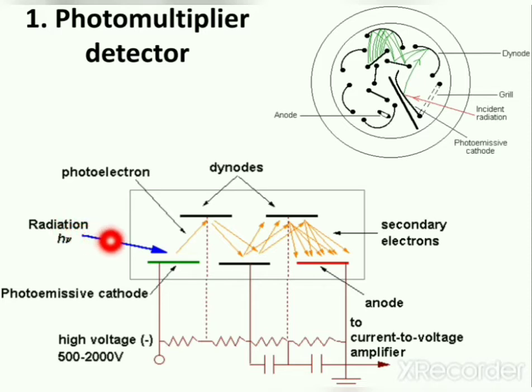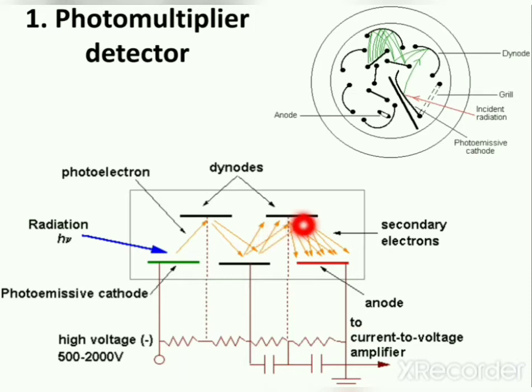The last component is the collector electrode, which collects the electrons. When radiation coming from the sample strikes the first photoemissive cathode, it results in generation of electrons. These electrons are attracted by the dynodes, which are fixed each with increasing potential. The electron strikes the first dynode, causing multiplication of electrons; these are then attracted by successive dynodes causing further multiplication. At last, the multiplied electrons are collected by the collector electrode, and the signal produced is the fingerprint of analysis of the sample under investigation.